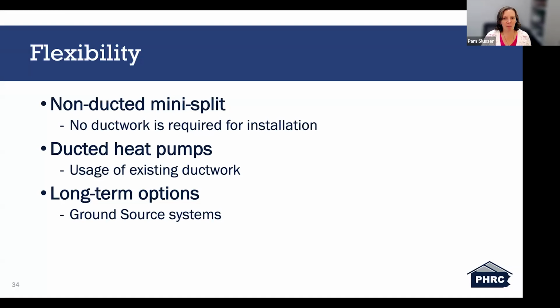And then ducted heat pumps, they can be a great option when installing the system in a home that already has ductwork installed. You want to be sure to check the existing ductwork, replace as needed or upgrade if larger is required. It's a good idea to do calculations and make sure the existing ductwork is up to capacity.